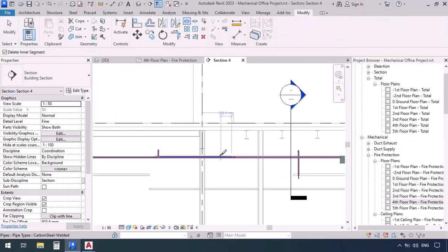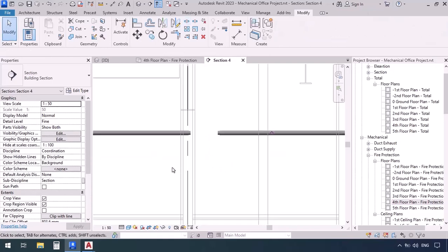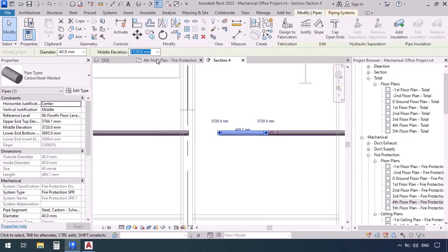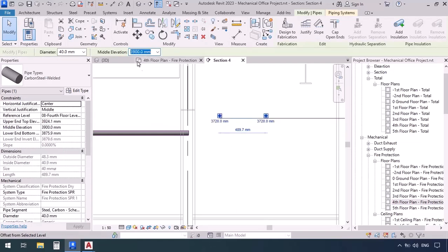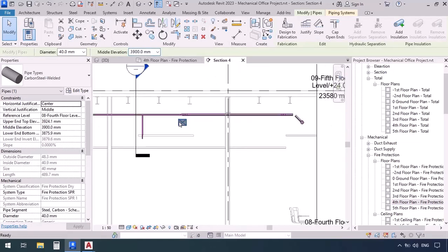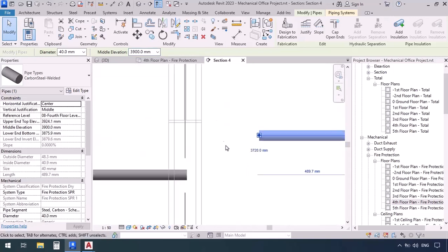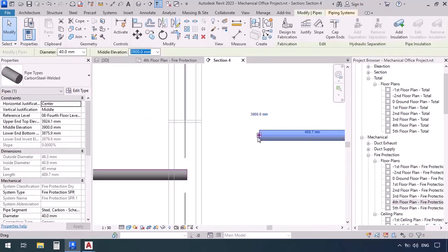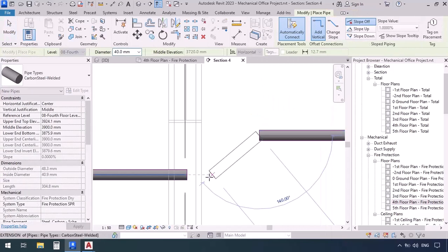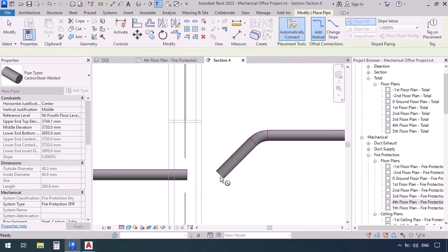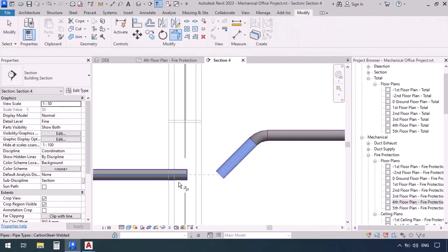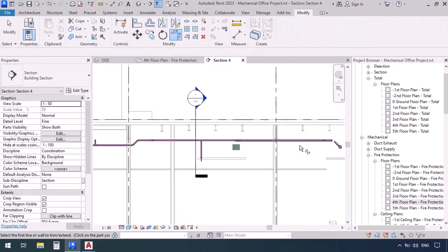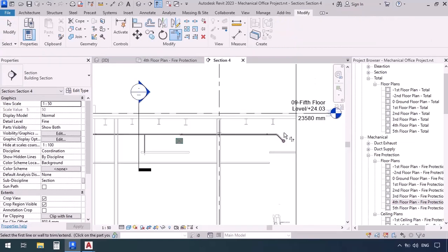From here on out we're gonna lower the elevation, but the part before it would stay at elevation 3,900. So again I'm gonna split the pipe right here. And then I'm gonna select the unions and delete them. Then set this pipe's elevation at 3,900. And now that it went higher it's no longer crossing the duct right here. And now we're just gonna connect these pipes. Right click and draw pipe. And at a 45 degree angle. Then use trim to connect them together.